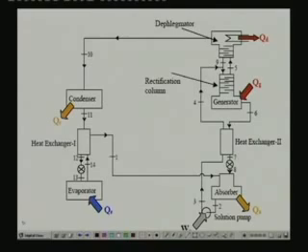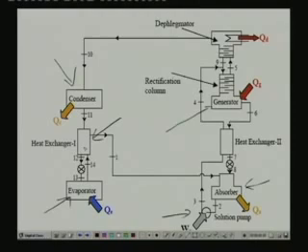Okay. So, as I mentioned, you have the basic components here: the evaporator, condenser, absorber, solution pump and generator. In addition to these basic components, you also have an additional heat exchanger here, a subcooling heat exchanger, and you have what is known as a dephlegmator here, and you also have a rectifying column. The rest of the components are similar, like your solution pump, expansion valve, liquid suction heat exchanger. All these components are similar to water lithium bromide systems.